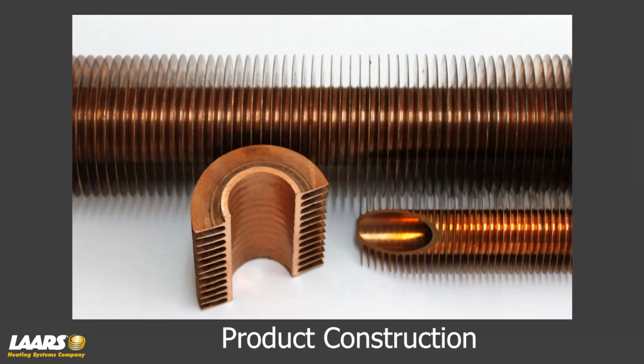There are a couple different materials we use. Copper fin. So this is a fin tube design heat exchanger. We're showing copper fin tubes here. And we also have this in cupro-nickel for volume water heating. Cupro-nickel is a harder material. So if you had a volume water heating application where you had hard water, you could install a hard water pump. That hard water pump would force the velocity through the tubes to keep those tubes clean. That way you don't lime up a tube. So again, on V models or volume water heating models, that would be cupro-nickel.